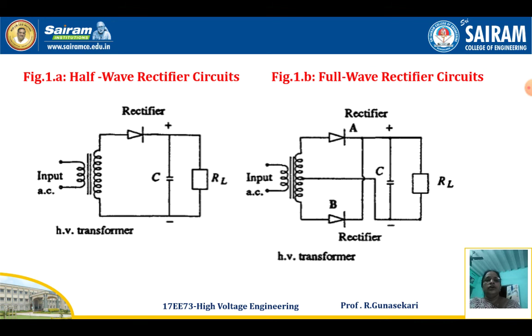If you want to protect the various elements from the forces, the anode is fixed to the wall cover on one side. The cathode and the filament are located on the other side. I told you, 50 kV and above means we are using rectifier valves. The rectifier valves consist of anode, cathode and filament. So the anode is fixed to the wall cover on one side, and the cathode and filament are located on the other side. A steel mesh structure or protective grid kept at the cathode potential surrounds them, so that the mechanical forces between the anode and the cathode are reflected on the grid structure only.